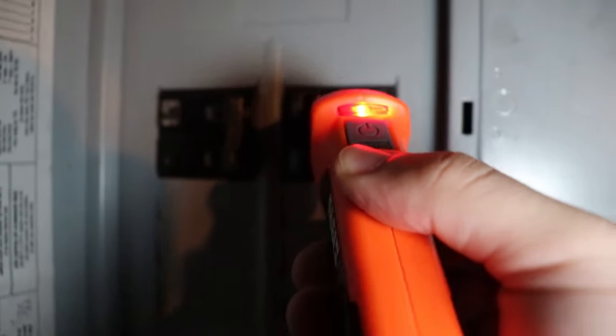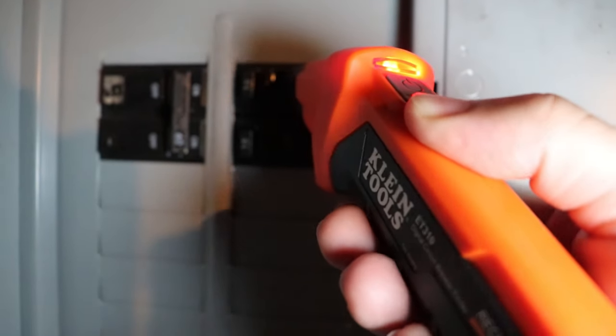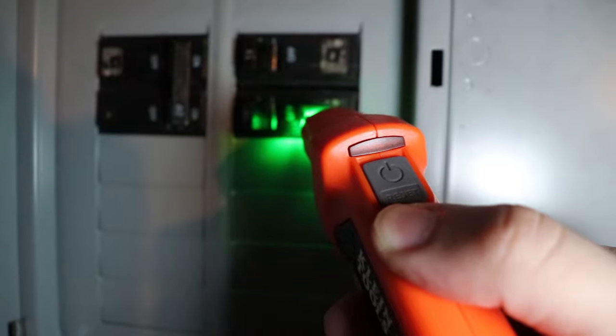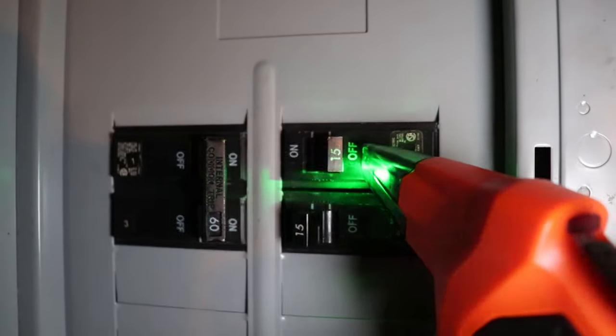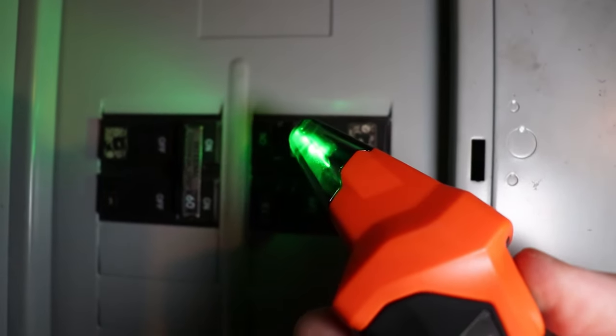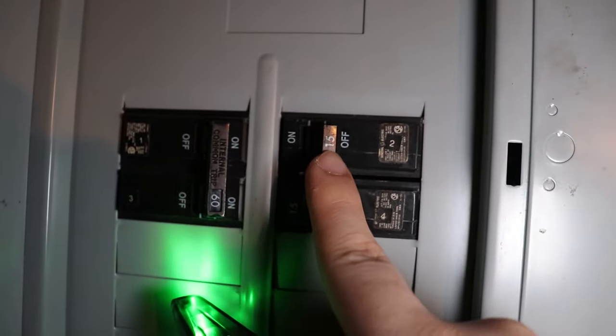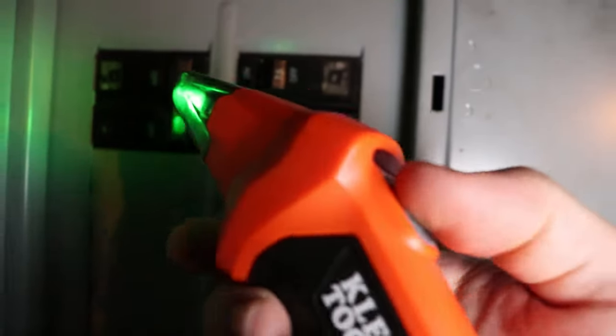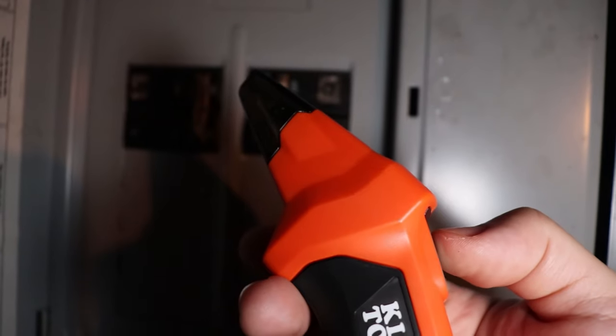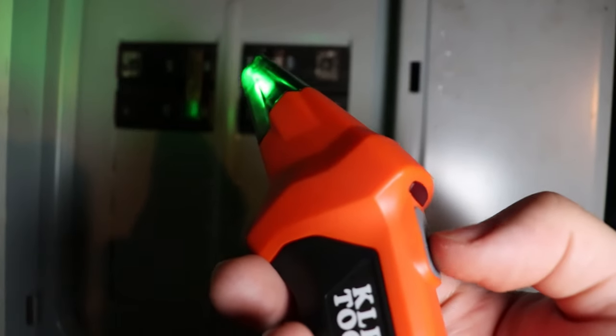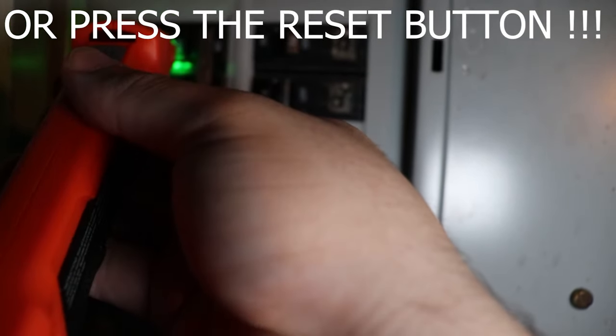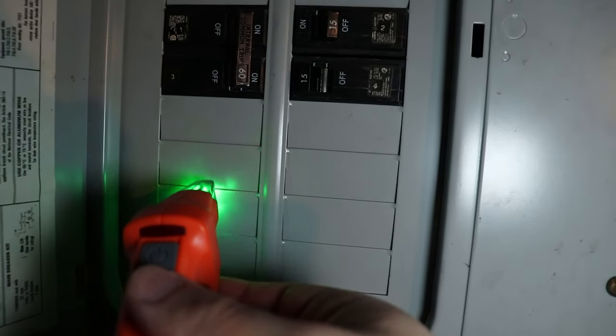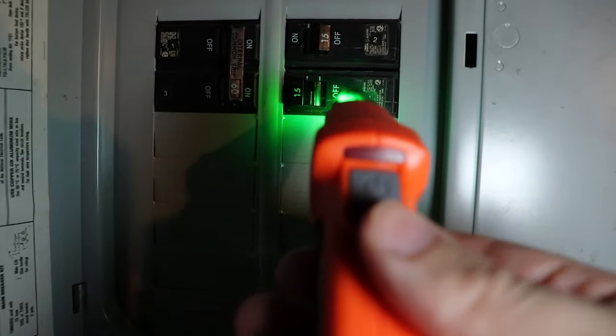And as you can see, that is our winner. Just to be sure, once we get the one that has our receiver screaming and we turn it off, there's now no issue. And if you want to make sure, which is recommended by Klein, turn off your receiver, turn it on again just to make sure you didn't get a false positive. And you're going to go slowly through however many circuits you have.